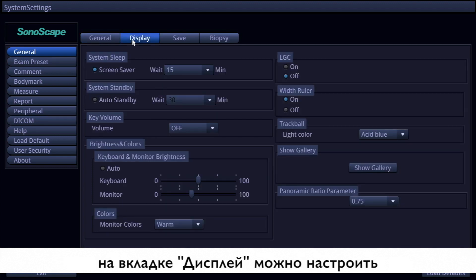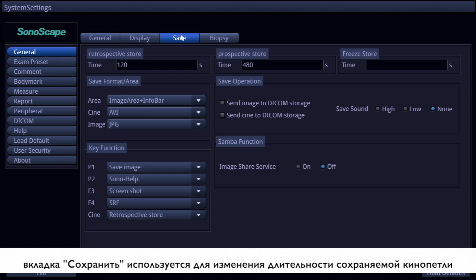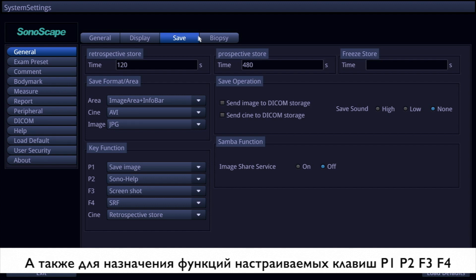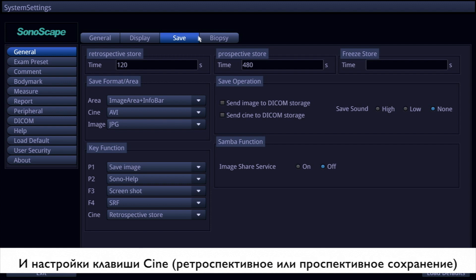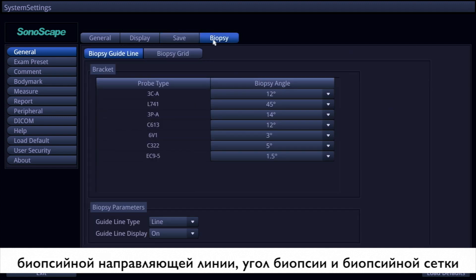On the display page, you can change display settings according to customer preference. The save page is more commonly used — on this page you can change the storage settings and also the key functions of P1, P2, F3, F4, and CINE can be changed here. The biopsy settings including biopsy guidelines and biopsy grid are found on the biopsy page.